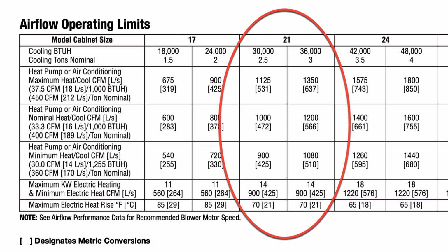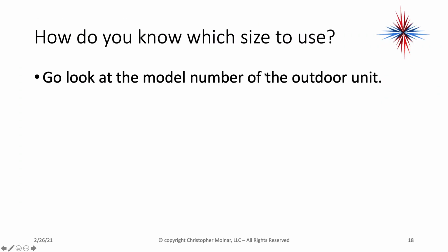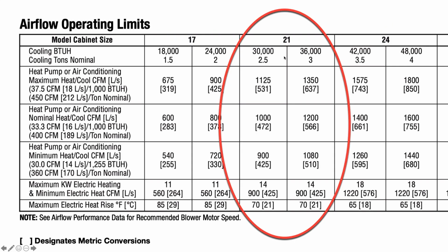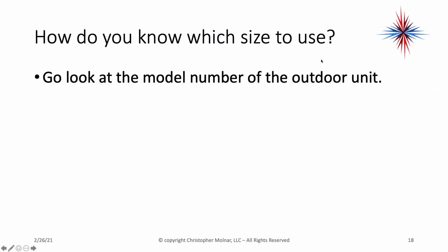If I set a system up with minimums, it's only going to get worse as time goes on. The other thing you have to look at is the minimum CFMs for the electric heat that's installed. If I go under 900 CFM, my electric heat strips are going to start overheating and it becomes a fire hazard. So always work with the nominal for the tonnage. Now, how do you know which size to use, 2.5 or 3? Go look at the condenser, the outdoor unit of the heat pump.